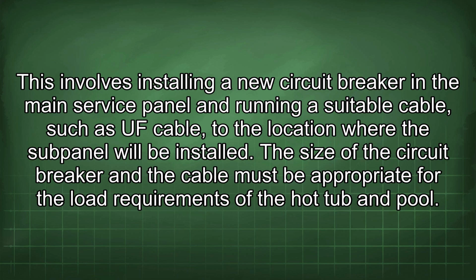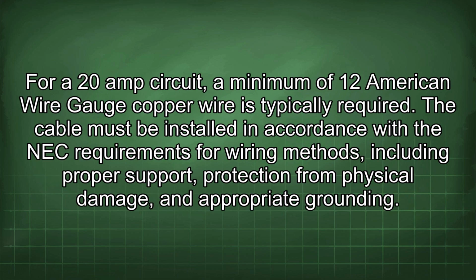The size of the circuit breaker and the cable must be appropriate for the load requirements of the hot tub and pool. For a 20 amp circuit, a minimum of 12 American wire gauge copper wire is typically required.